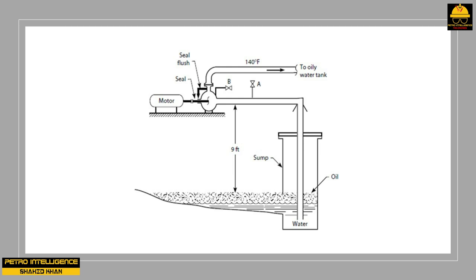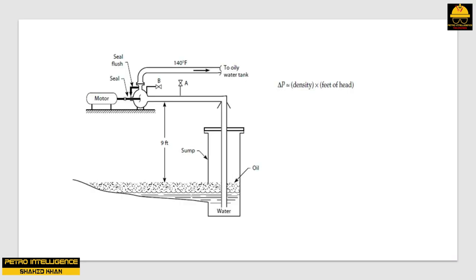After the fix, the pump would continue running for about an hour after it stopped raining, producing a discharge pressure of about 100 PSI G. Then quite suddenly, discharge pressure would drop to 70 PSI G and the amp load would slip from 20 to 14 amps for its last few minutes. The cause was that the water level in the sump had dropped and a layer of oil with a specific gravity of 0.70 had been drawn into the suction. The feet of head developed by the pump had not changed, but pump discharge pressure is proportional to density times feet of head. As the specific gravity dropped by 30%, so did the discharge pressure; amperage is also proportional to the weight of liquid pumped.